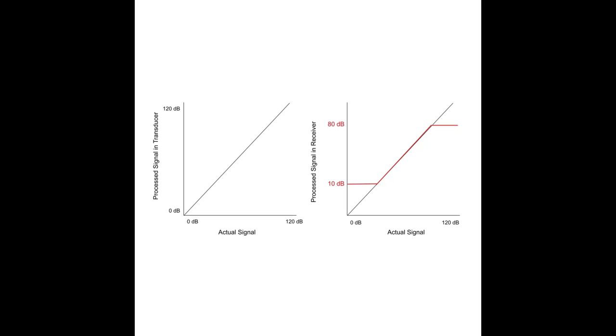The important part is that the weak signals are still on the weak side and strong signals are still on the strong side. The transducer can handle analog signals from 0 to 120 decibels. The receiver, with a dynamic range of 70 (80 to 10), needs anything below 10 to be amplified up to 10 — those 2, 3, 4 decibel signals are amplified to 10, still on the weak side — and anything stronger than 80 is reduced down to 80, still on the strong side. We have compressed the values from a range of 120 down to 70, keeping weak weak and strong strong, so no errors are introduced. That is first compression.